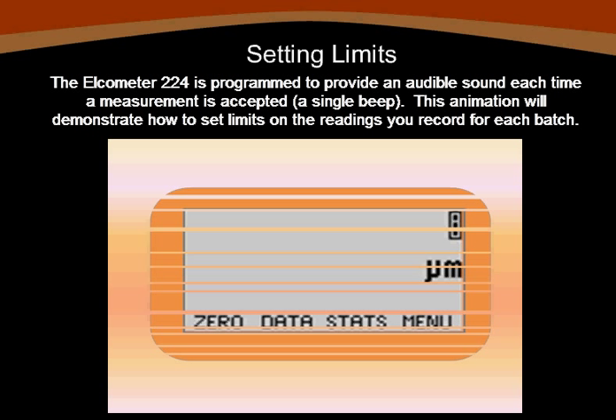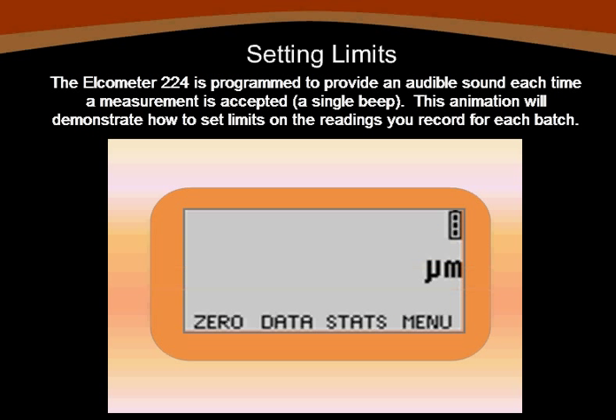The first step in defining your reading limits is selecting the data option from your main LCD display. Remember that the 224 is equipped with an audible alarm which will notify you if a reading should fall outside your limit range. Arrow down to set limits and press the key.